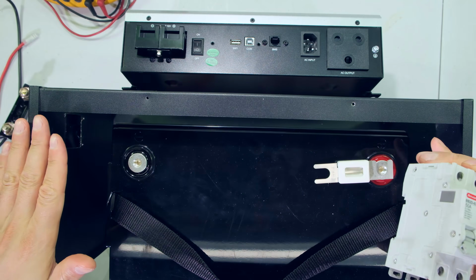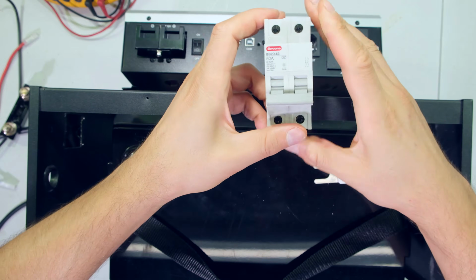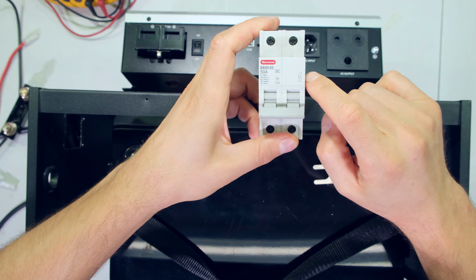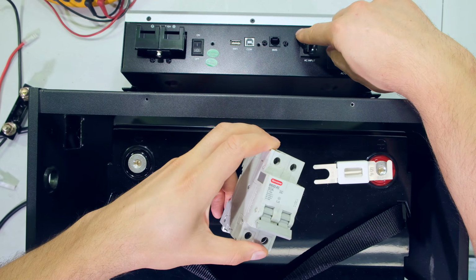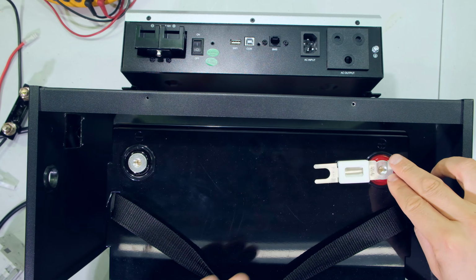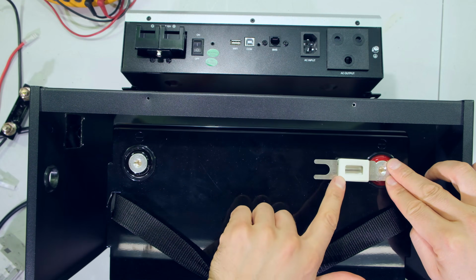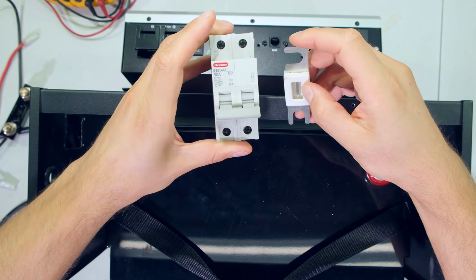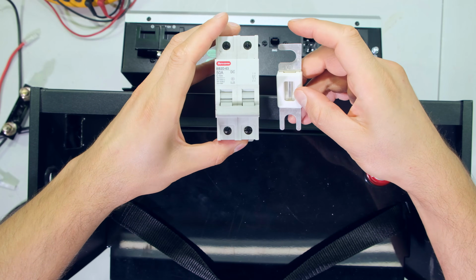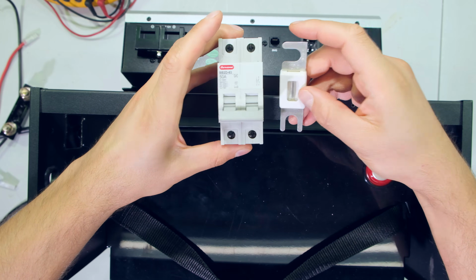So because I have this box, I can now mount the circuit breaker on the side of the box so that if the inverter has a fault, the circuit breaker will trip. If I don't want to use a circuit breaker, I can simply use a fuse in line with the inverter. All right, so I'm going to go through the specifications of the inverter to select a fuse or a circuit breaker or even both.